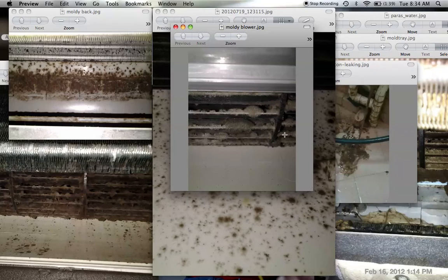In general servicing, somebody comes, takes a vacuum, and tries to vacuum away these mold particles. Trust me, a lot of technicians are not aware that these are mold. They may think these are dust particles and say, hey, your estate is very dusty. But trust me, this is not dust, this is mold. Look at the shape of this fella. How do you know if it's mold or not? We've been in this industry for more than 10 years and we've seen so many aircons before.